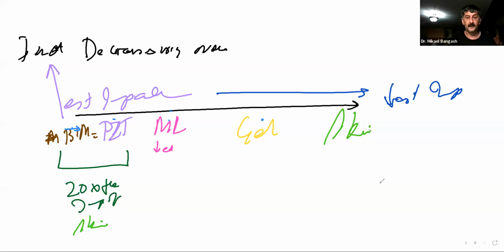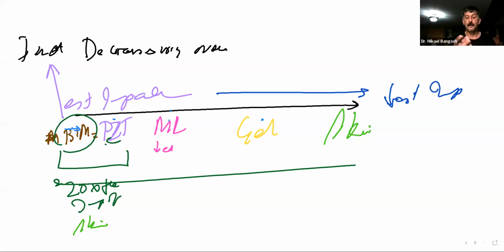Whereas please keep in mind that during reception, if it asks where does the sound wave end up, after the matching layer, it's going to end up in the piezoelectrical material. And after the piezoelectrical material, in the backing material, and so on.